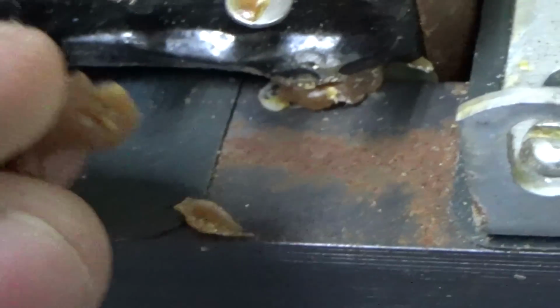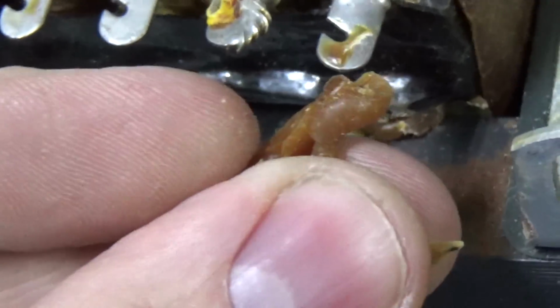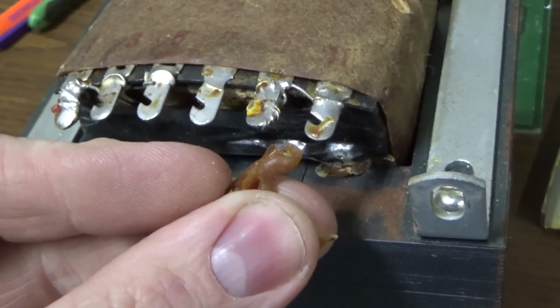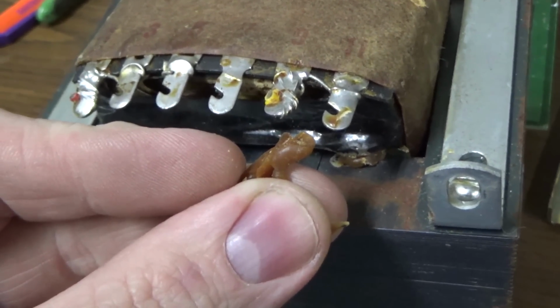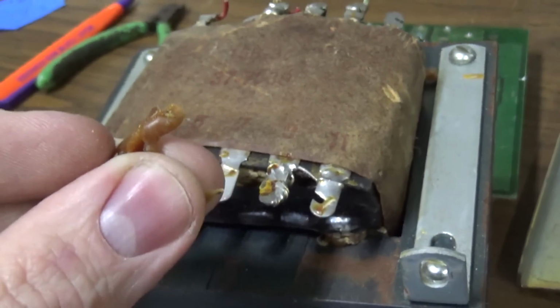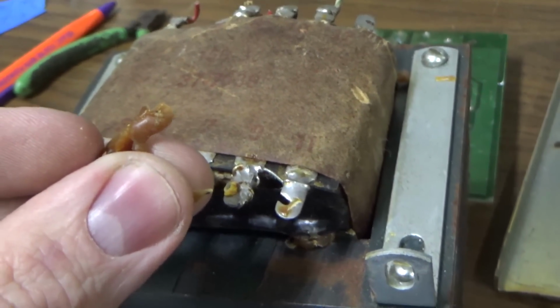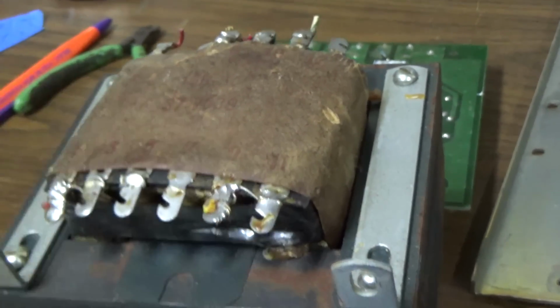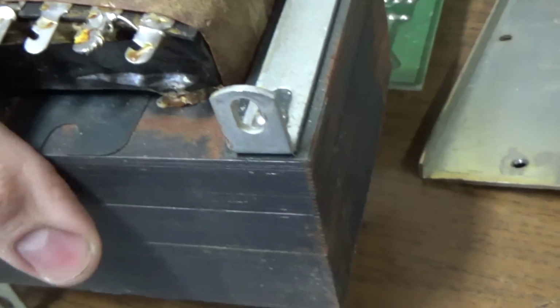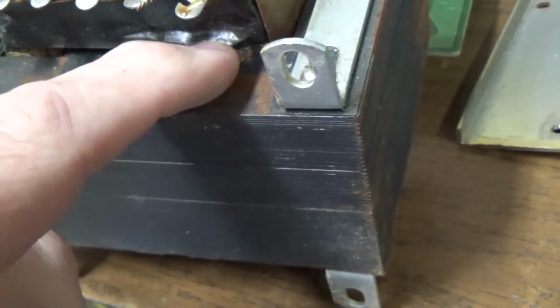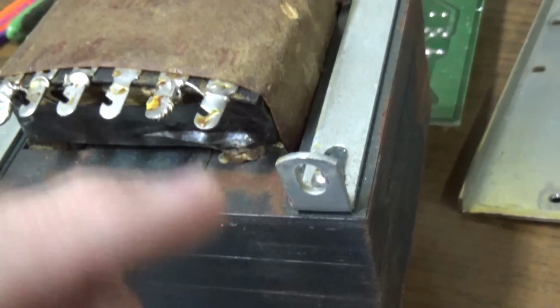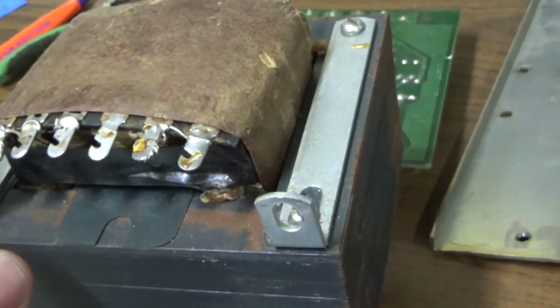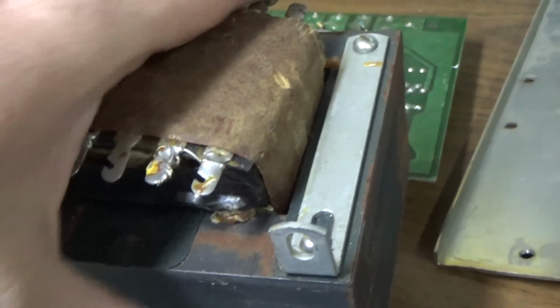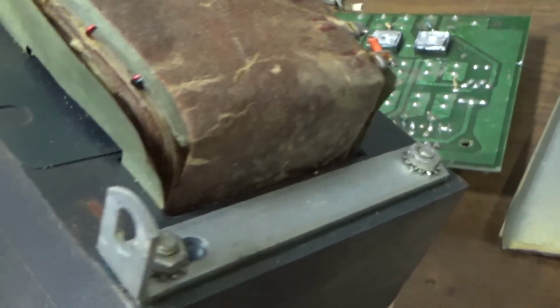So we may end up in a situation where this thing is shorted. If you see a little bit of it, it usually doesn't necessarily mean that the thing is shorted, but it means that it got hot. It's possible to see this and the thing still be fine, but that's what that is—wax that has leaked out because it got so hot that it liquefied and started leaking out of the transformer.